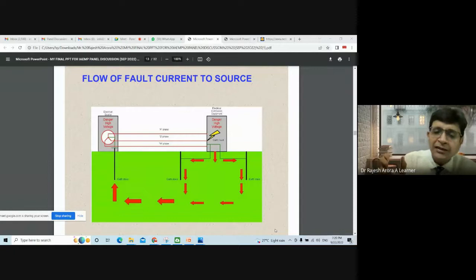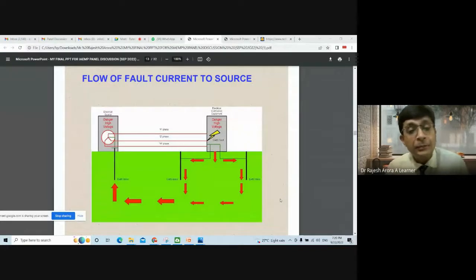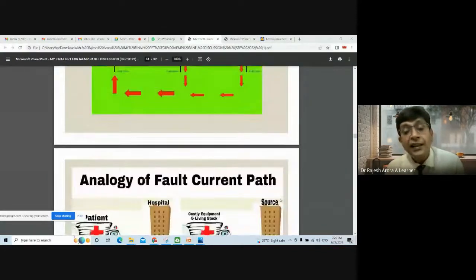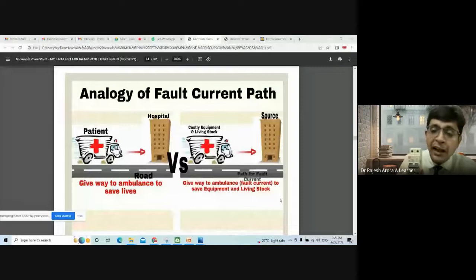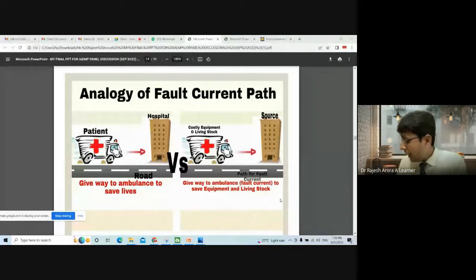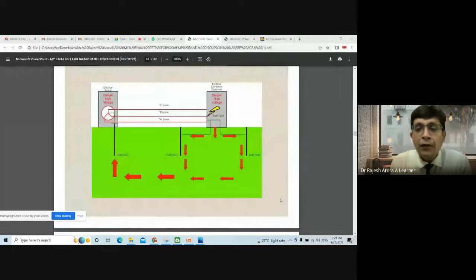For residential purposes, that should be 30 milliampere. At the same time, when you're talking about protection systems against short circuit and fault current, be careful while choosing the MCB. That should be B type, not C type or D type. When you choose the B type MCB, it means it will operate at 3 to 5 times the rated current. When you use C type, it will operate at 5 to 10 times. When it is D, it is 10 to 20 times. And I'm quite sure D type and C type, in case of requirement, fail to operate and become a cause of fire.